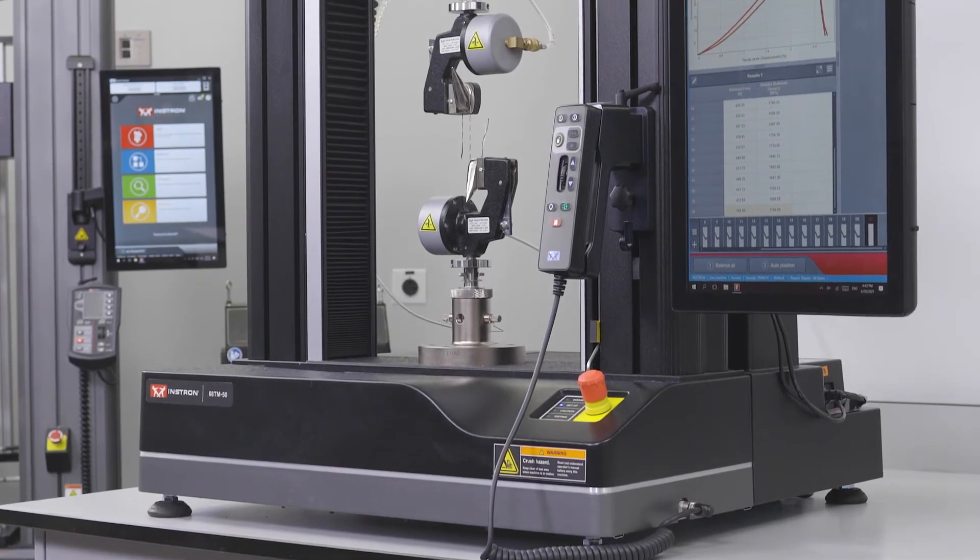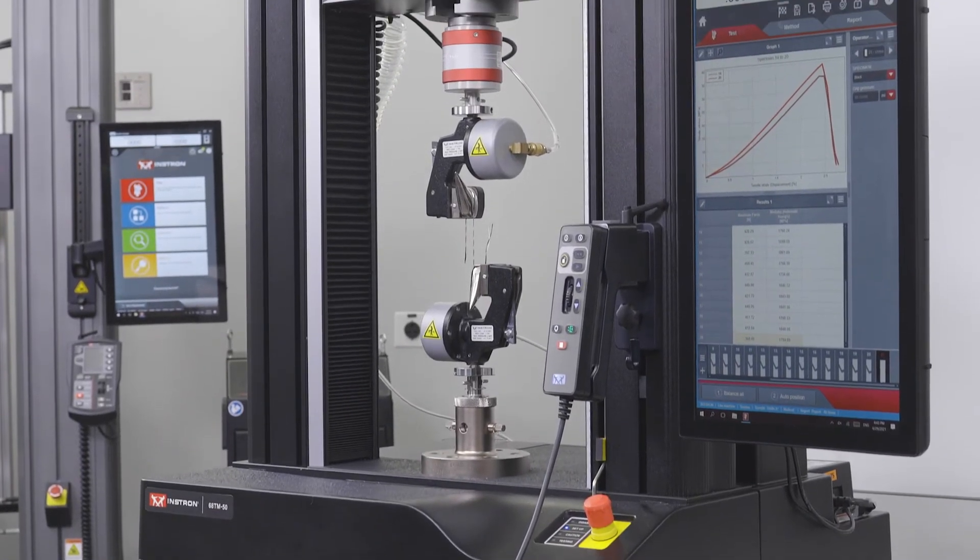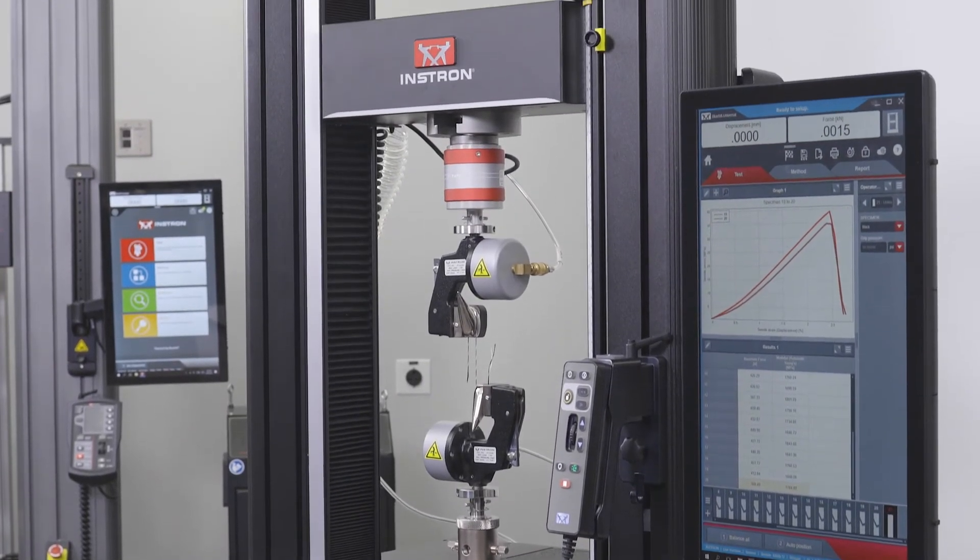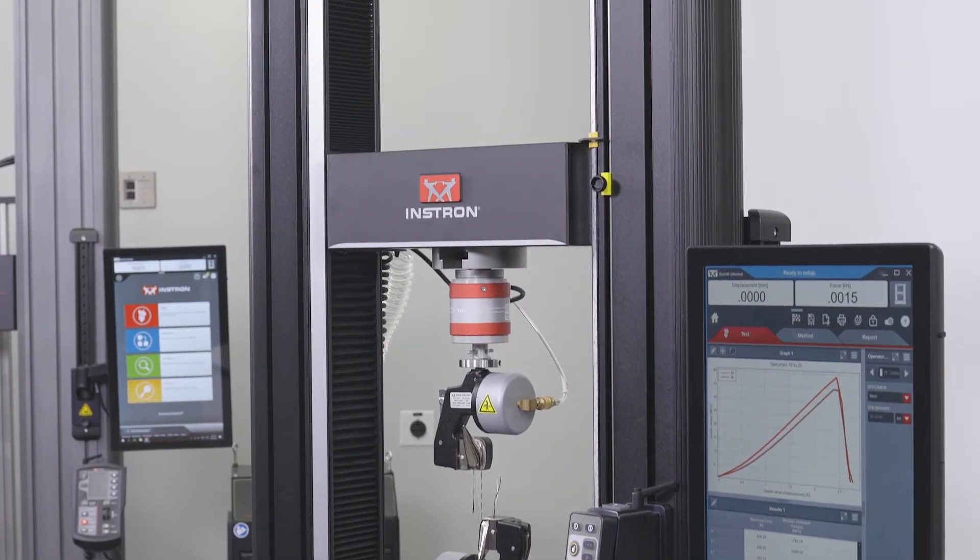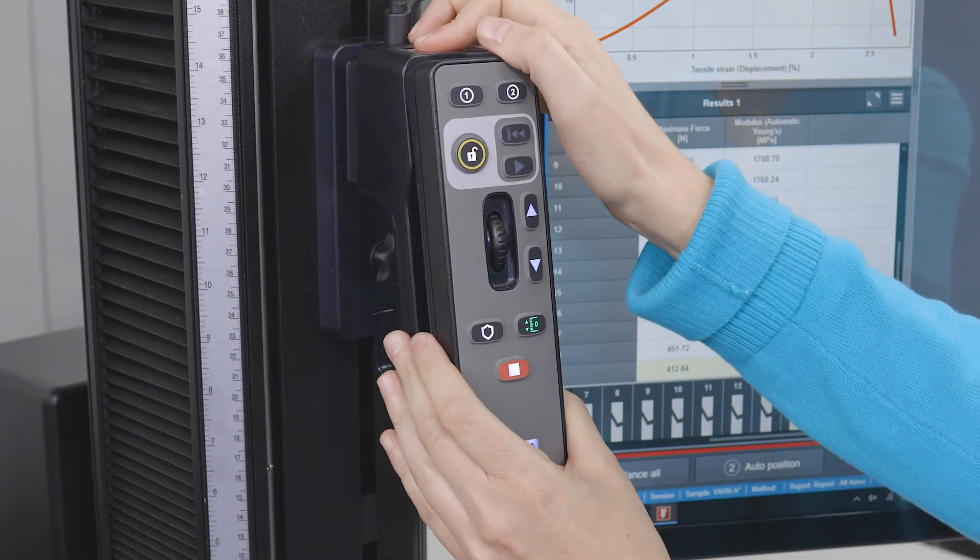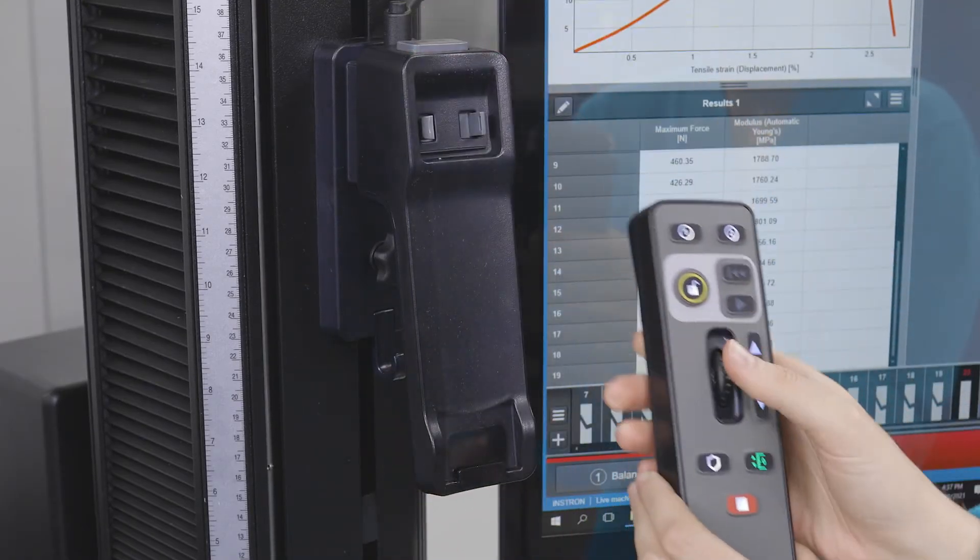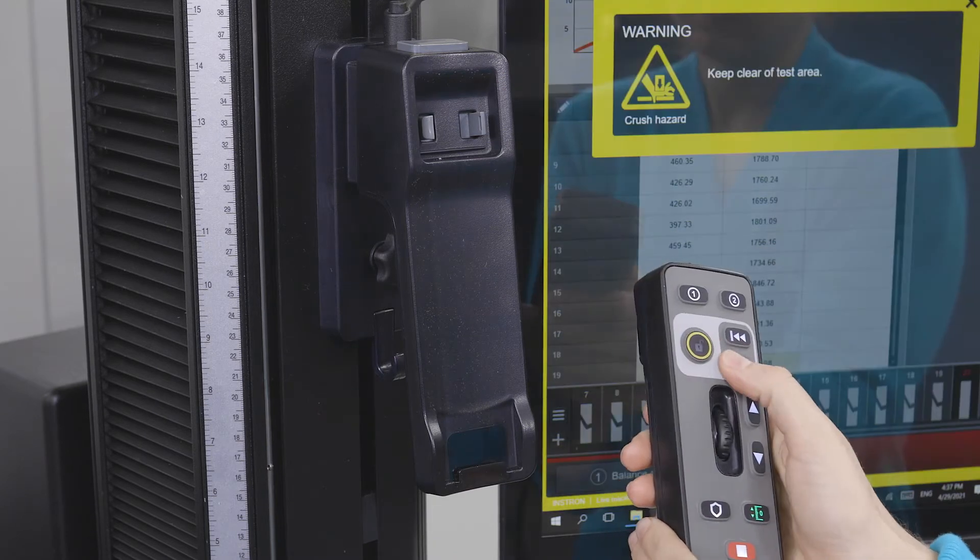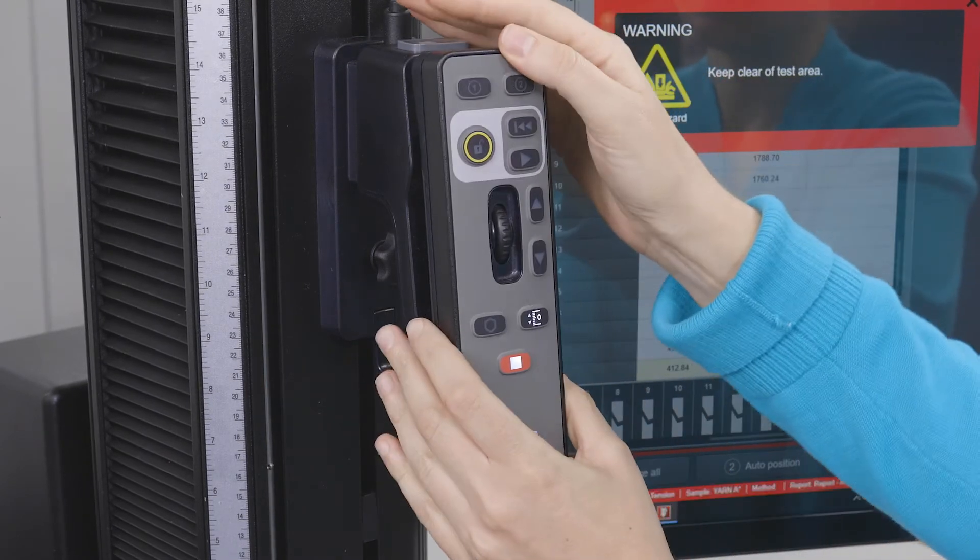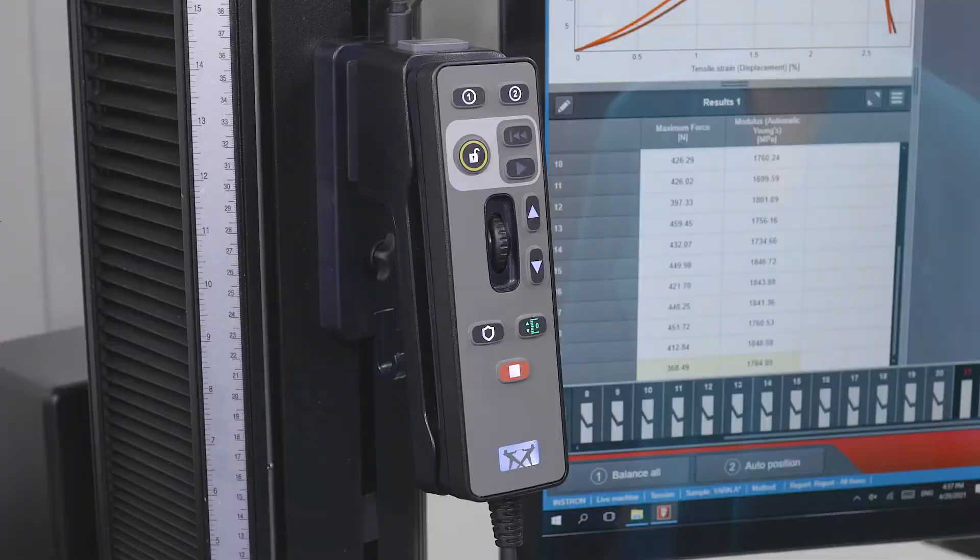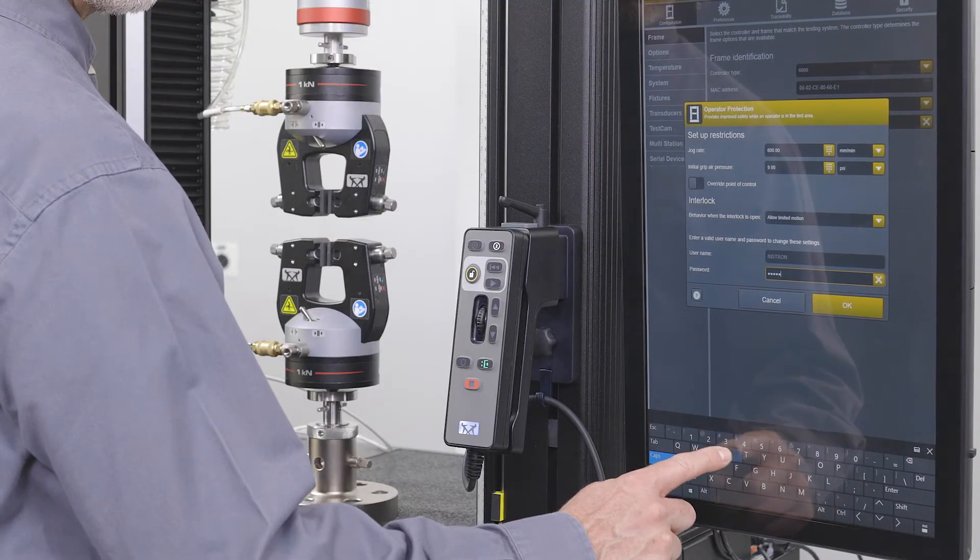On 6800 series systems, the machine can only be controlled from a handset, which includes the virtual interlock button used to begin a test. This ensures a safer testing experience by adding intentionality into the workflow and reducing the likelihood of unintentional frame movement.